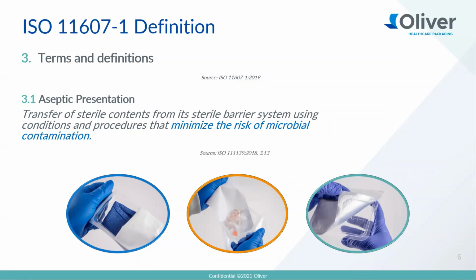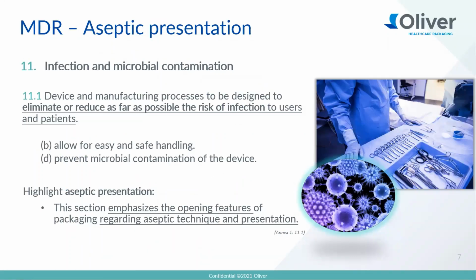Yeah, for sure, Jeff, that's a good point. So Jeff, if we now look at the definition of aseptic presentation from the MDR perspective, specifically if we look at section 11, it states that the device and manufacturing processes are to be designed to eliminate or reduce as far as possible the risk of infection to users and patients. You're right, Tommy. And sections B and D talk about allowing for ease and safe handling of the device and also to prevent microbial contamination of the device.